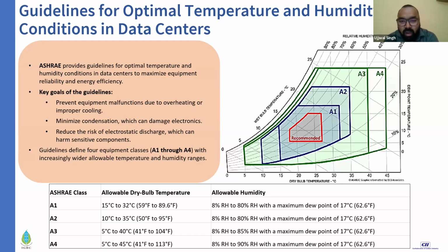I'll tell you what happens when the humidity goes too low or too high in data centers. If the humidity goes too low, there's a chance of generating an electrostatic discharge. Electrostatic discharge is when you stand on some woolen cloth and rub your feet, and then you touch something, there's a small spark between your finger and that surface. That is electrostatic discharge, generated because of the potential difference between you and that surface. A similar thing can happen in data centers, and a large electrostatic discharge can short circuit the components and can even cause fires.